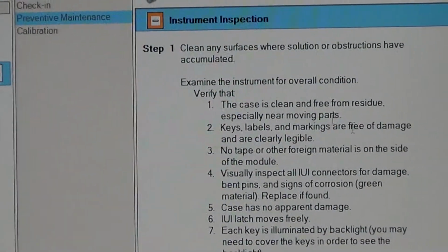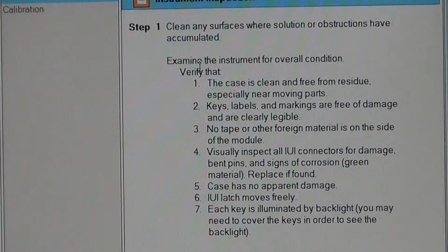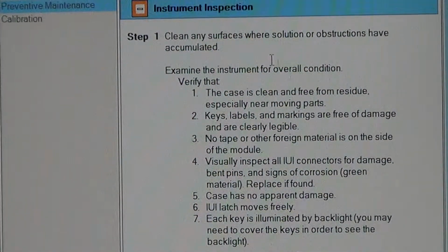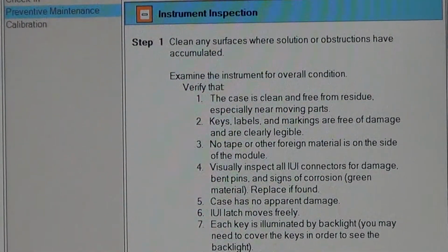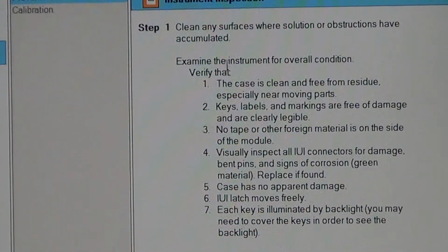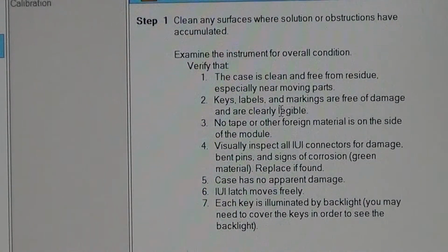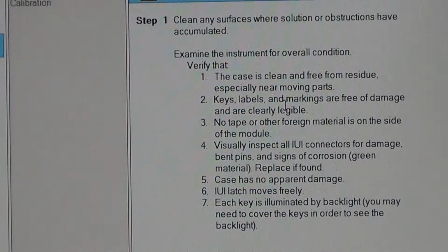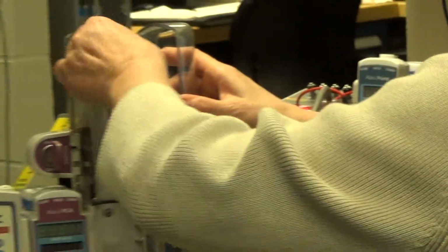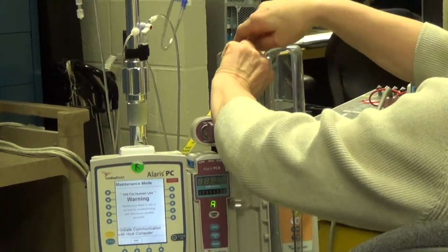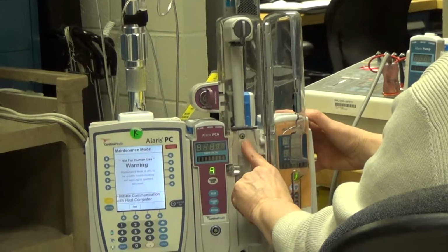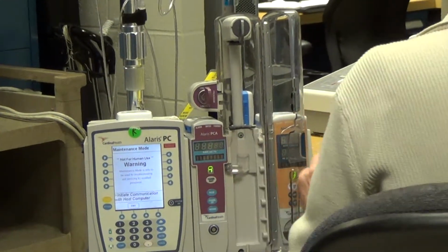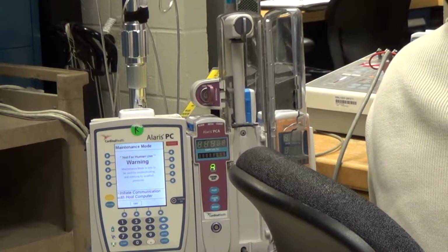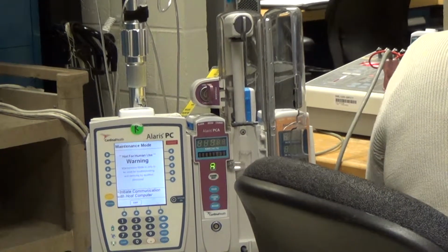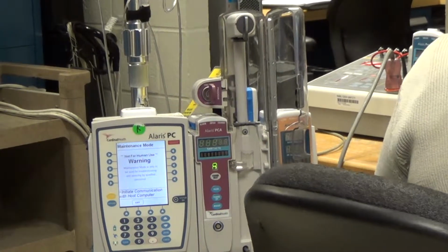On the right side of the window, you can see what tasks are called to be done. This is a step-by-step guide of what needs to be done to make sure that everything is functional. You start to make sure that everything is clean, that all the moving parts are doing just that. You check the clamp, that it works. You check that the claw is usable and works, and that it can be manipulated up or down. You make sure that the flange detector works and responds, and you move on to the next part. On the next page, you check all these things and make sure that everything is moving correctly.